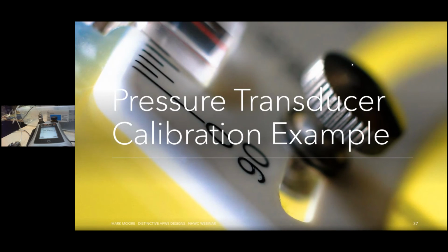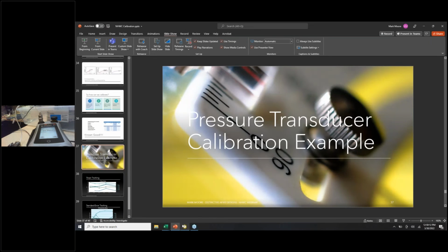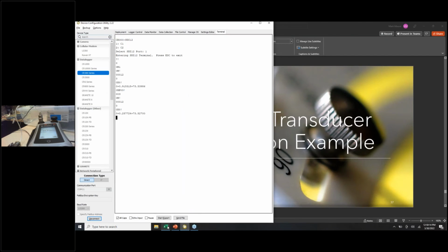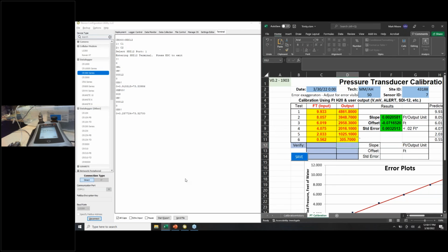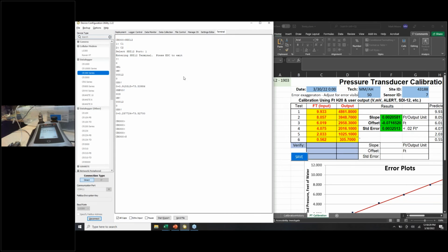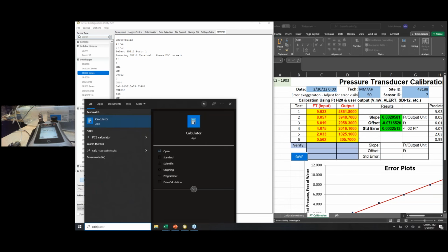I'm going to load up my screen. We're going to actually see the data from this PT and what it actually means. And I apologize that I don't have a way to make this screen bigger, so you're going to have to bear with me a little bit. What I'm going to do, let me clear this out, is I'm going to take measurements. This is an SDI12 PT in case you can't tell by the fact that it just said SDI12. I'm going to take measurements exactly when this PT calibrator reaches a level that I'm going to record.